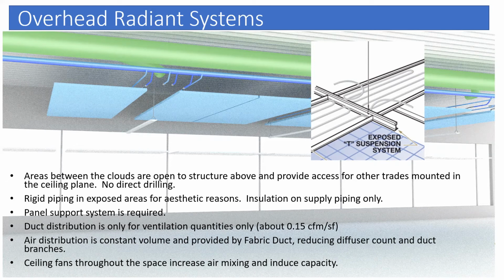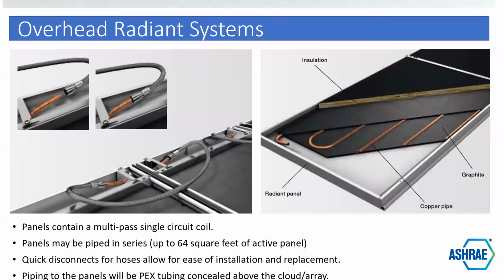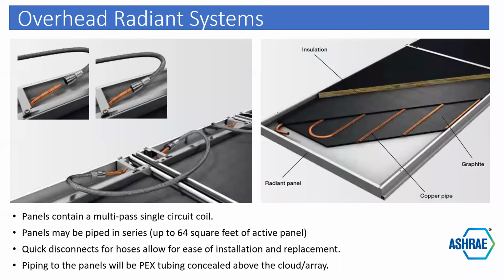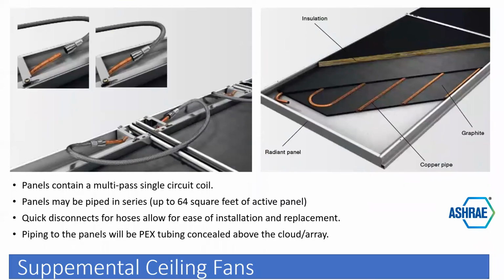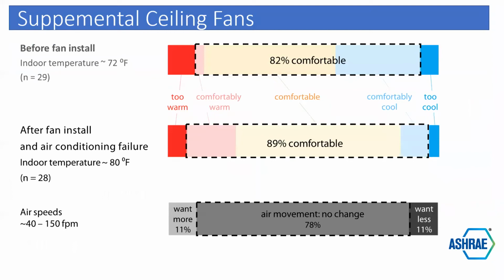In the open air, we're using a fabric style of ductwork, reducing diffuser count and duct branches, and ceiling fans throughout to improve comfort levels. And here's a sense of the ceiling panels with the copper pipe, the graphite, and the insulation. And before the fan install, the indoor air temperature at 72 degrees, we get about 82% comfort level. After the ceiling fans install, we can run the temperature up to 80 degrees Fahrenheit and get 89% comfort level.